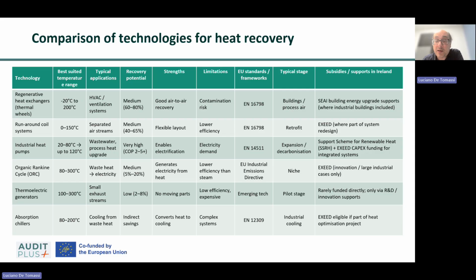Their key advantage is the complete separation of air streams, eliminating cross-contamination risks. However, their efficiency is lower than thermal wheel systems, and they require pumps, pipework, and additional controls. They are mature technologies and are eligible for support under ventilation and energy efficiency upgrade schemes. Industrial heat pumps are increasingly important for decarbonization and waste heat recovery.